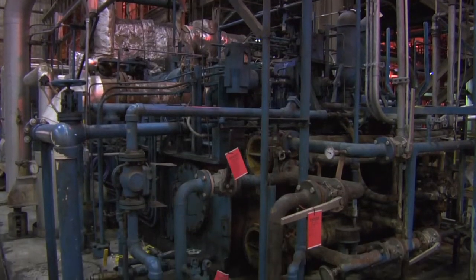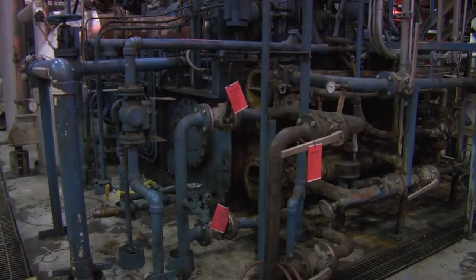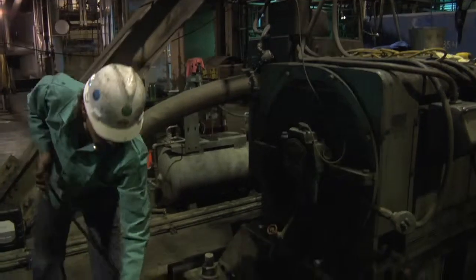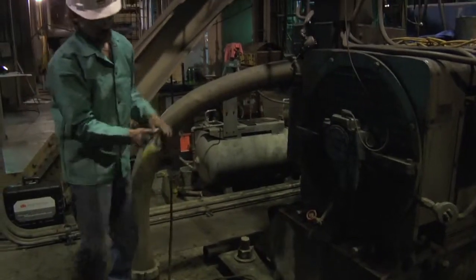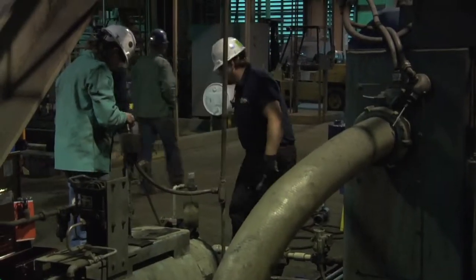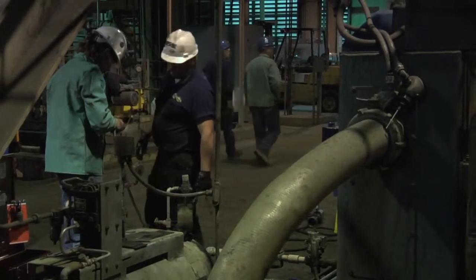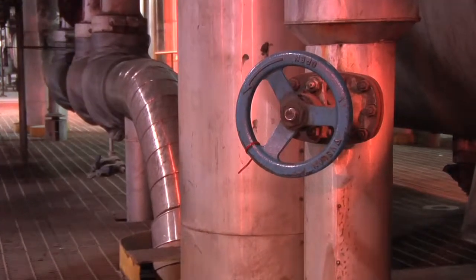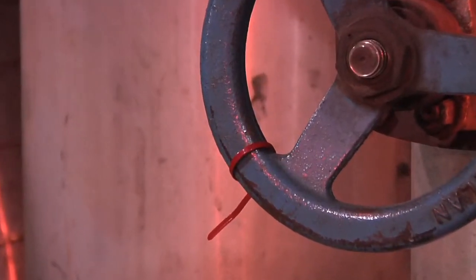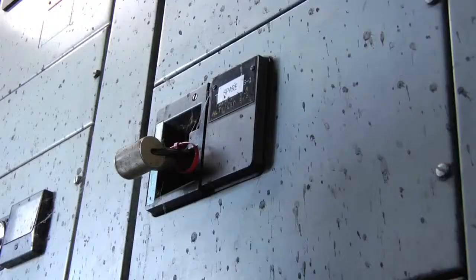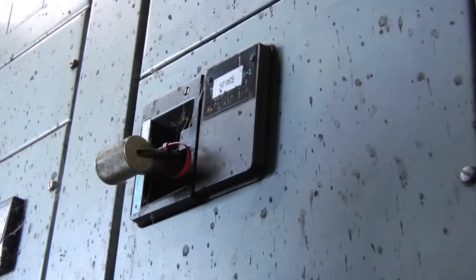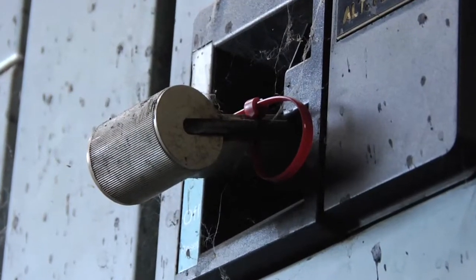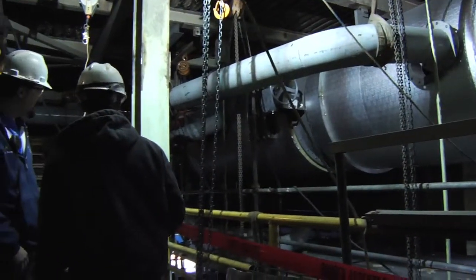Individual isolation tags are affixed to energy isolating devices using red plastic cable ties. Isolated devices with attached tags and cables shall never be operated, defeated, or otherwise bypassed. Equipment bearing only a red plastic cable tie shall be treated the same as equipment bearing a tag and cable tie. Red plastic cable ties will only be used for the permit clearance system. No other uses of red cable ties are acceptable at our facilities.